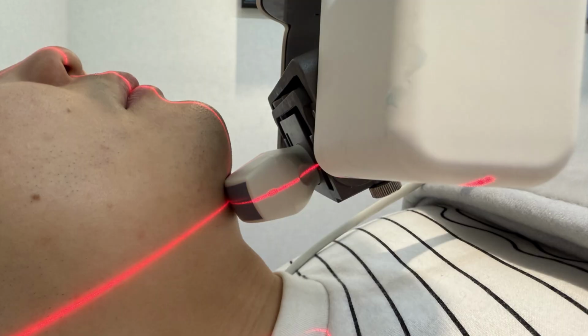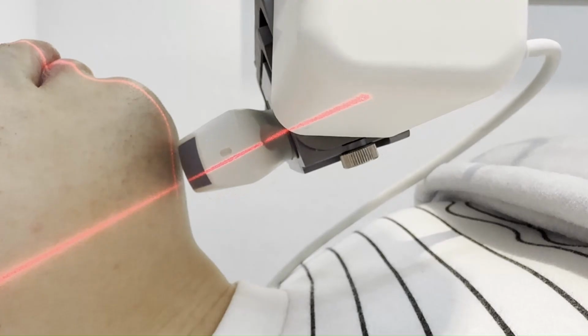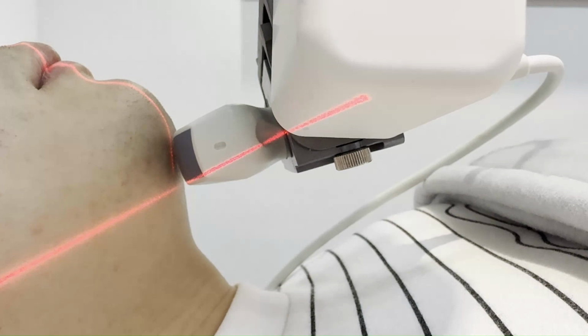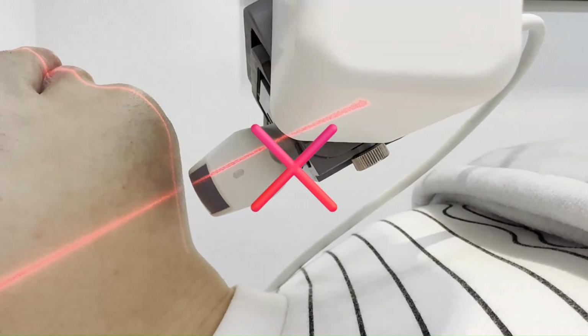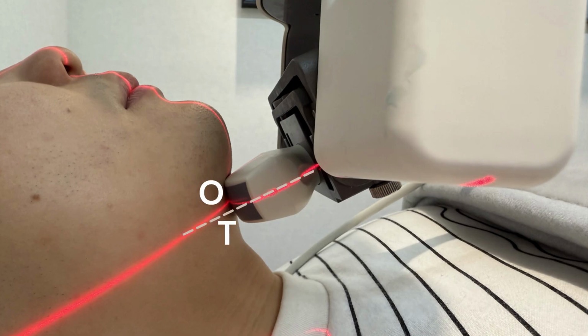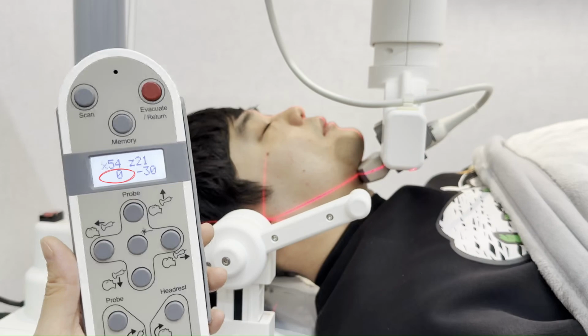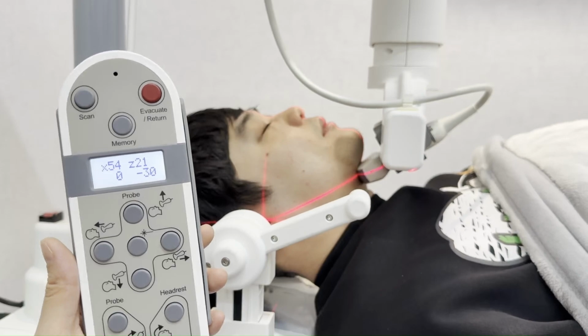Use the hand controller to guide the probe back to its initial position between the oropharynx O zone and base of the tongue base T zone. Position the probe so the HM plane laser intersects it at the midpoint, neither too high nor too low. While this serves as a general guide, you may need to adjust based on the ultrasound images displayed on screen. Watch contact force and keep near 0.